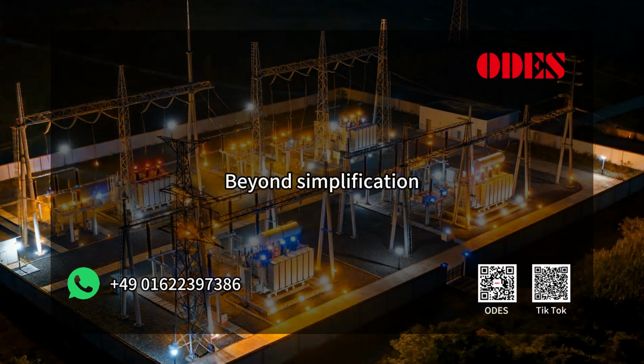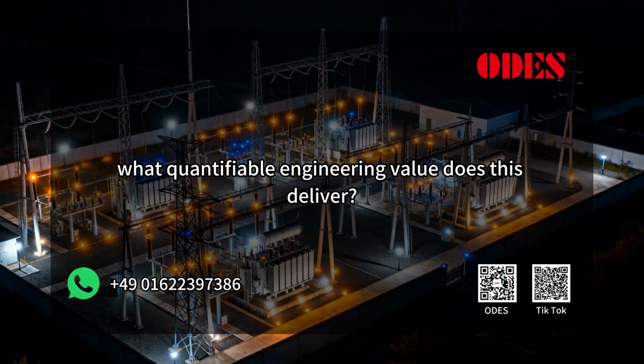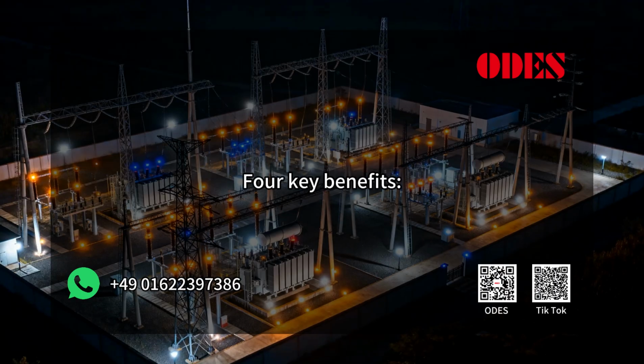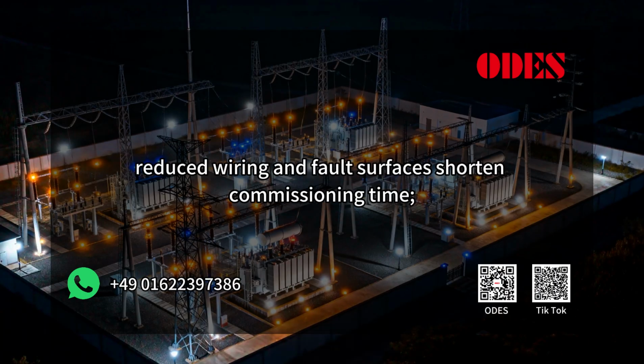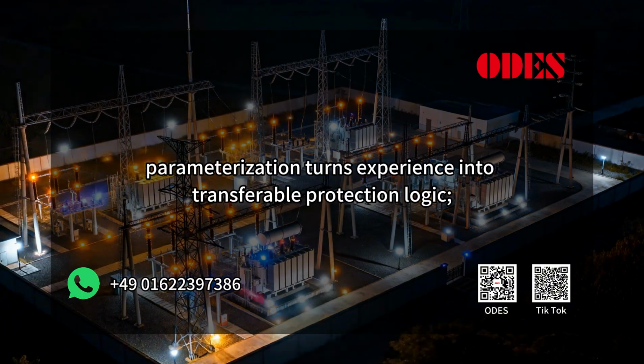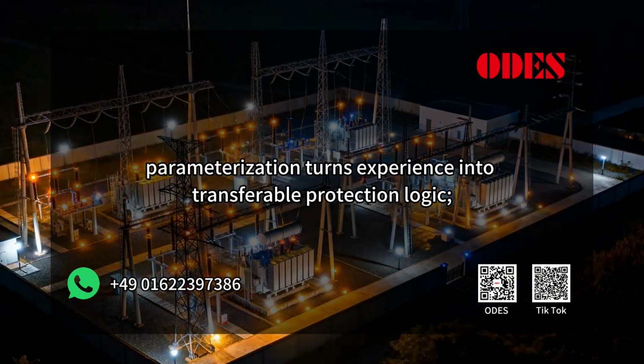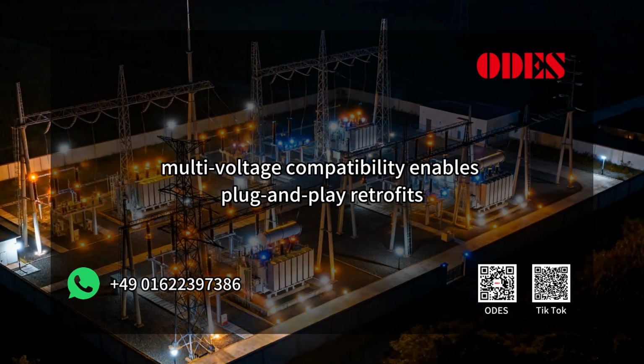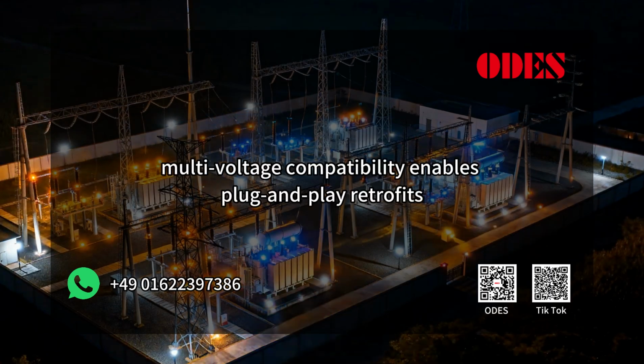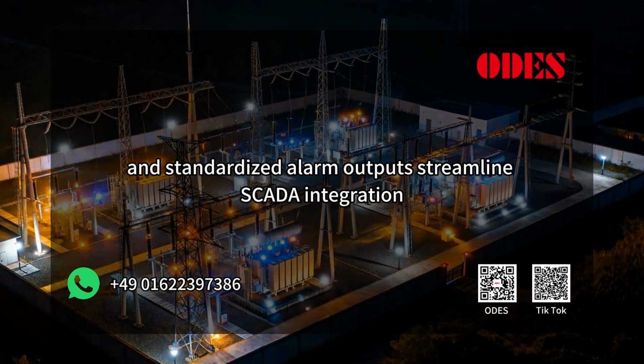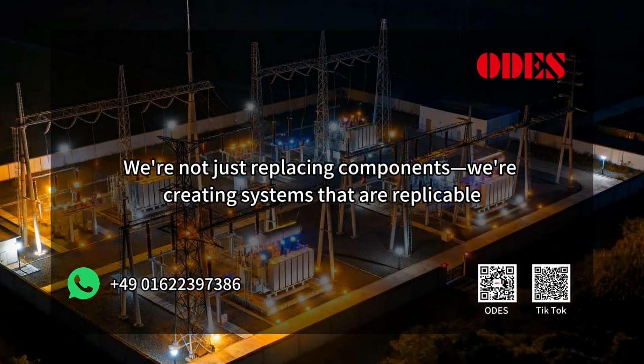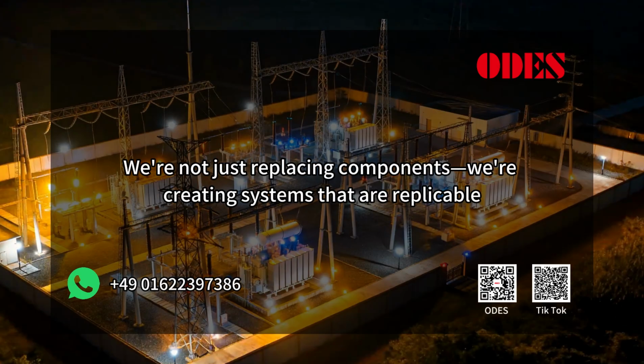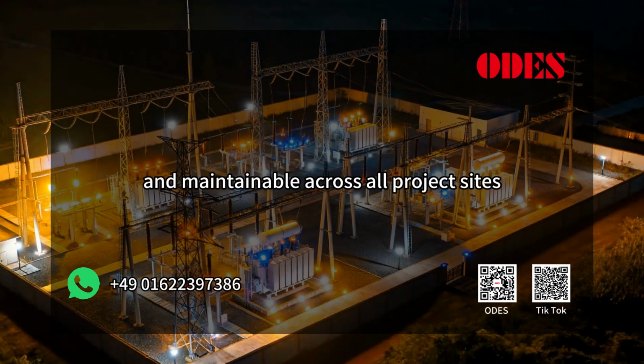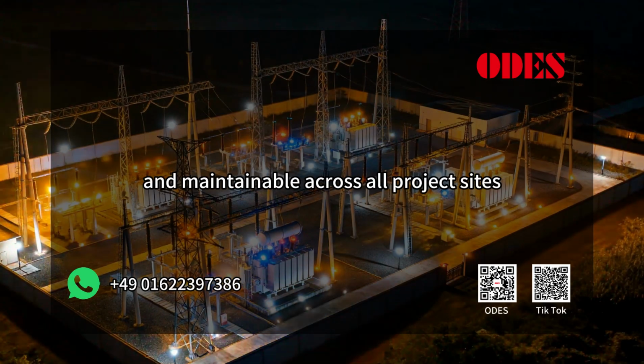Beyond simplification, what engineering value does this deliver? 4 key benefits: reduced wiring and fault surfaces, shortened commissioning time. Parameterization turns experience into transferable protection logic. Multi-voltage compatibility enables plug-and-play retrofits, streamlines SCADA integration. We're not just replacing components, we're creating systems that are replicable, diagnosable, and maintainable across all project sites.